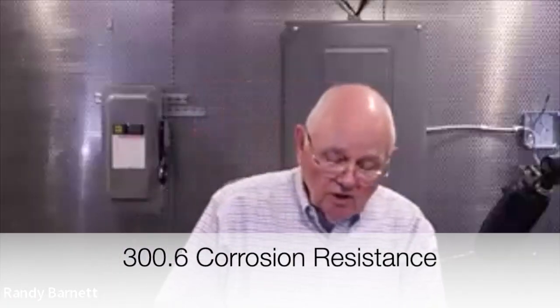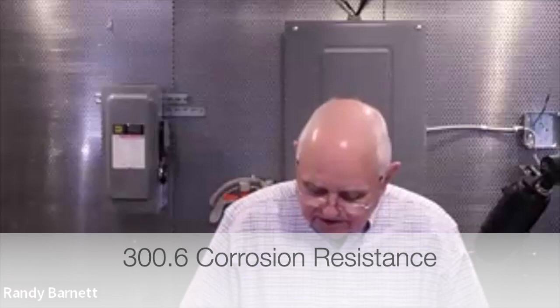And so, permanent and neat appearance. Anytime I install something like this, I have to assume it's going to be permanently installed. It's got to be neat in appearance as well, right? Adequate corrosion resistance. We've talked about that. 300.6 is a good reference in the code book for corrosion resistance. Now, this is kind of handy. It says generally screws are used on wood, masonry anchors on concrete or brick, toggle bolts similarly on hollow walls, and machine screws, bolts, or welded studs on steel.